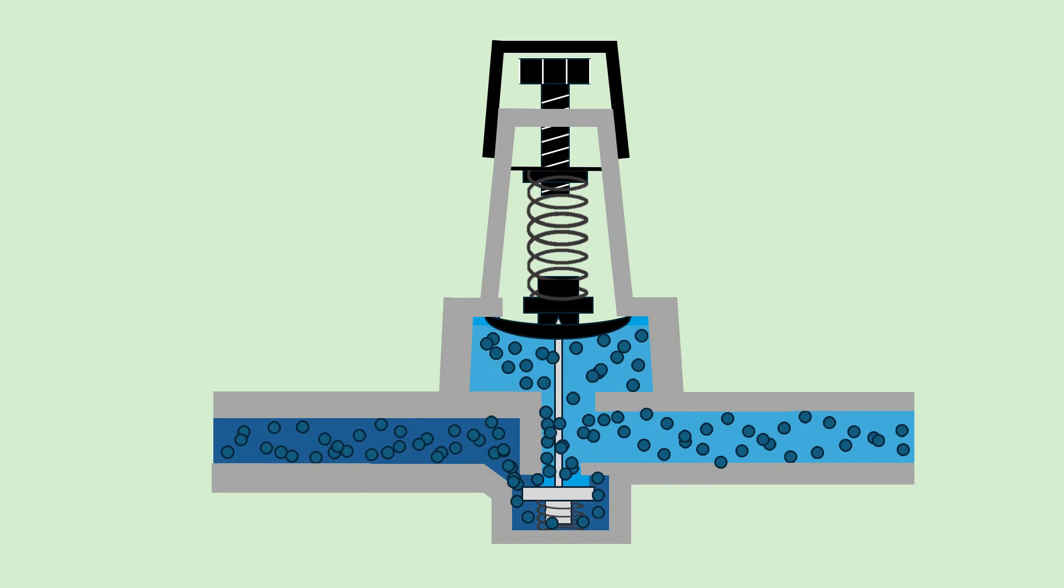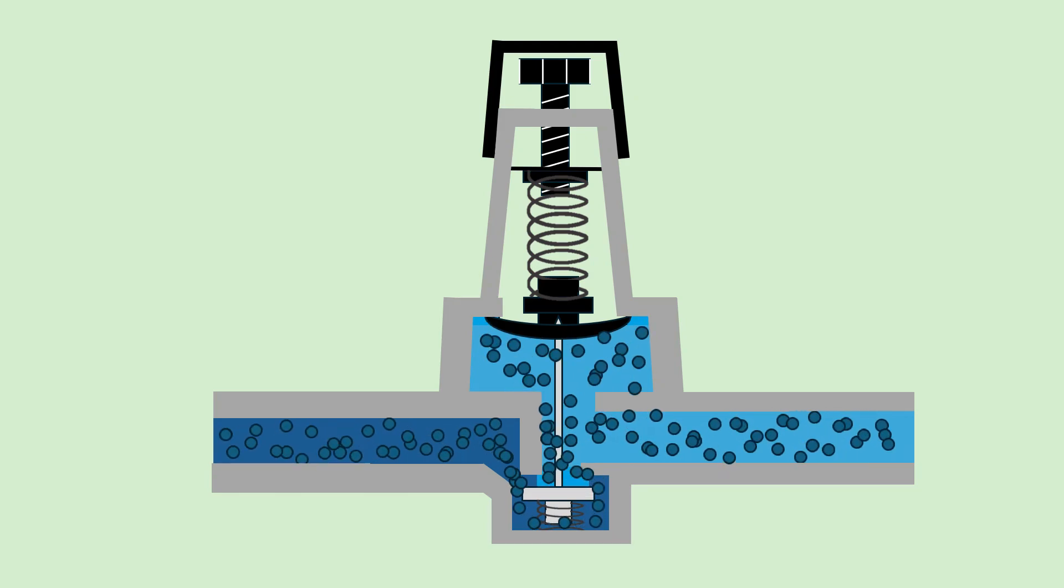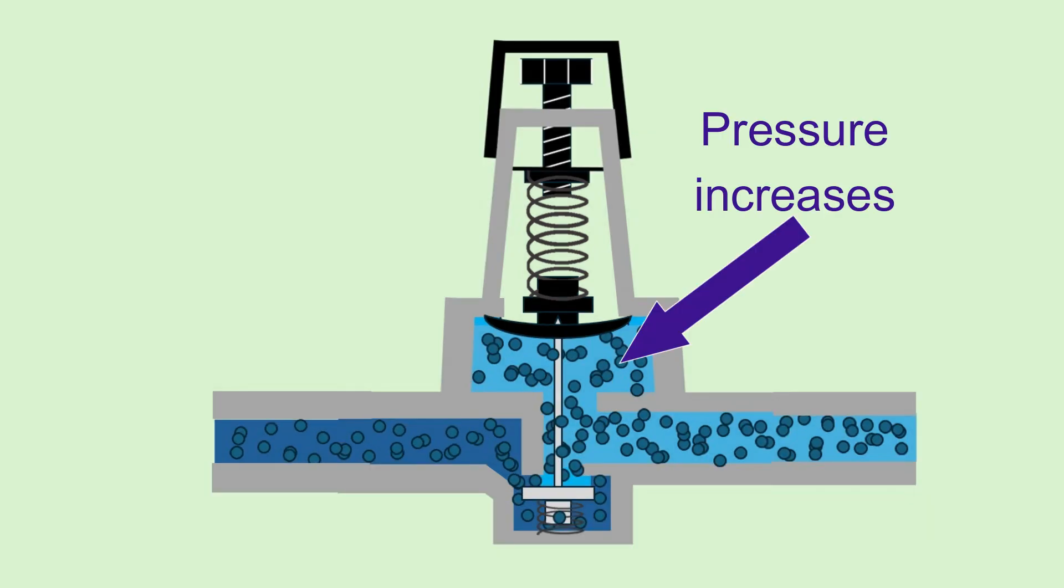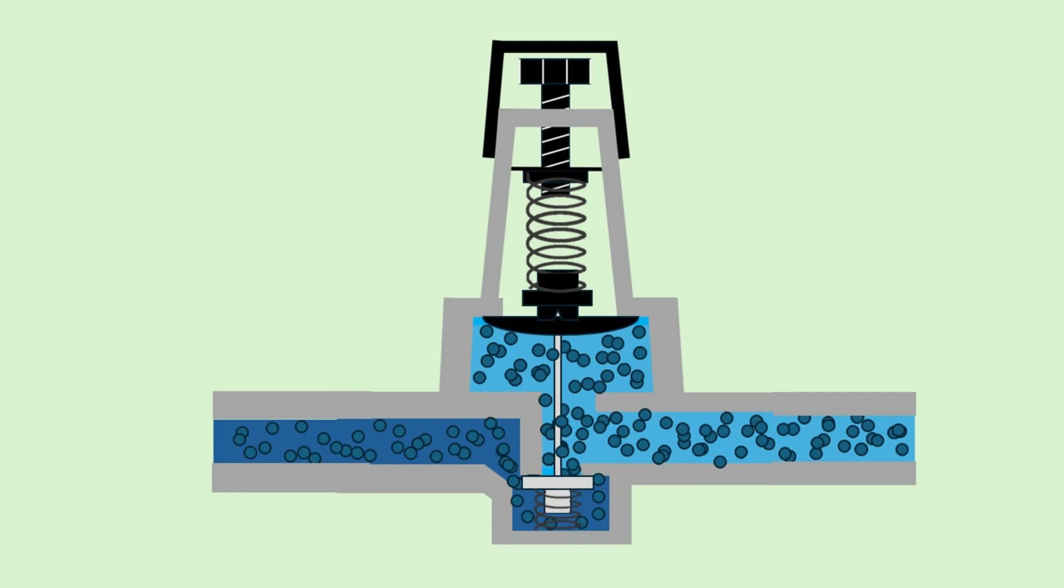Now let's look at another scenario that happens hundreds of times per day. Water is flowing through the PRV, and the faucet in the house is suddenly turned off. Let's watch how the pressure regulator reacts to this. As the water stops flowing, there will be an immediate increase in pressure on the outlet side of the valve. That higher pressure will quickly overcome the pressure of the adjusting spring and will push the diaphragm up.